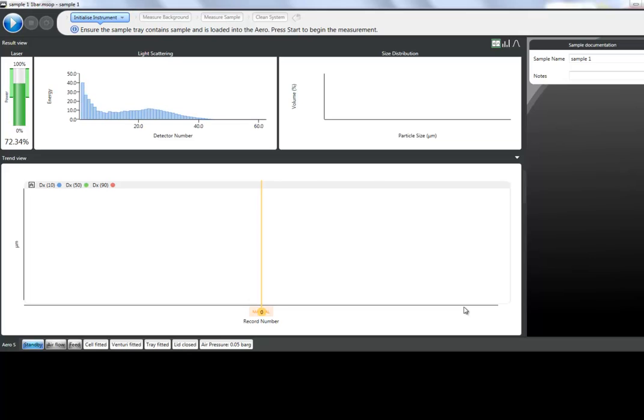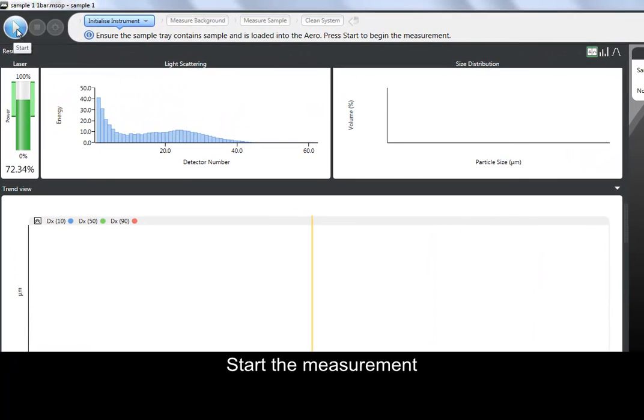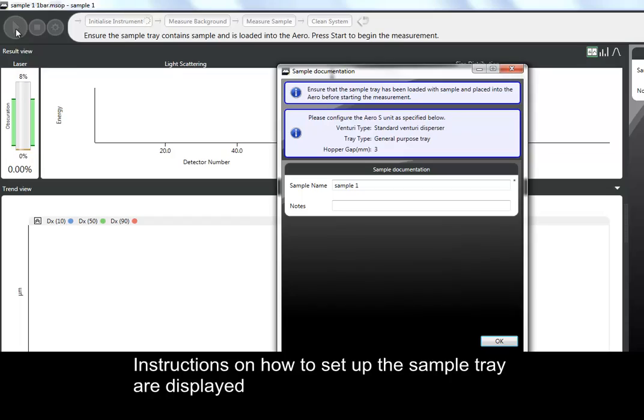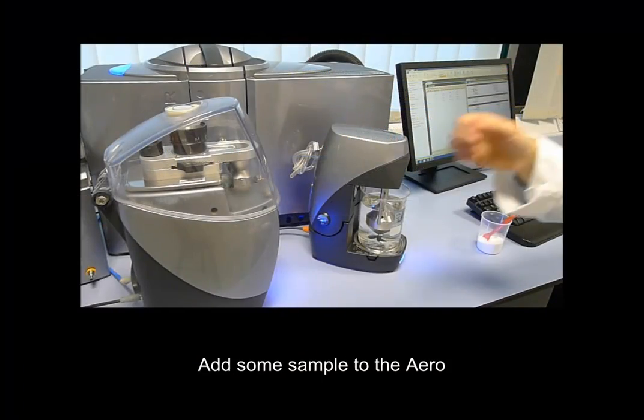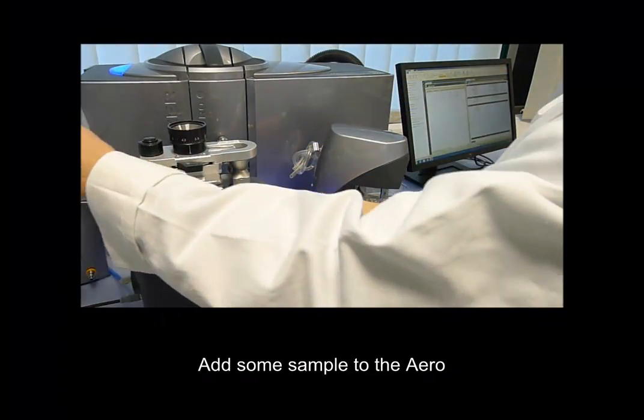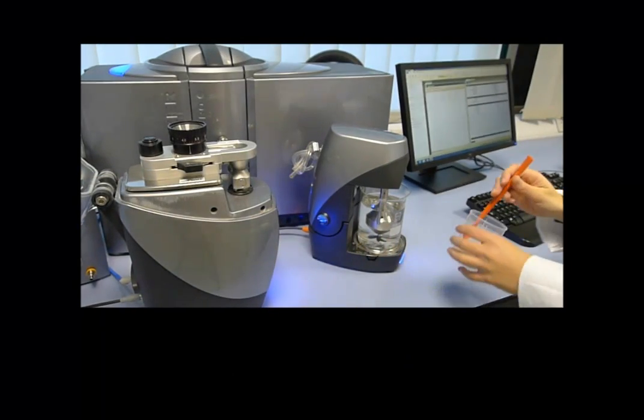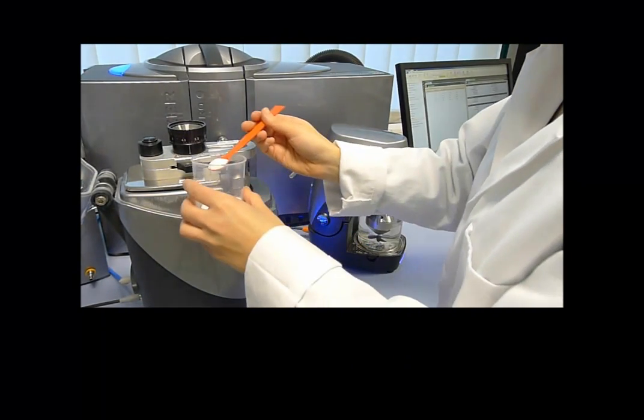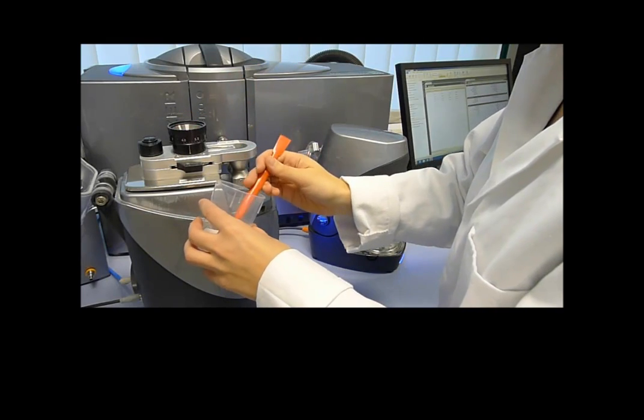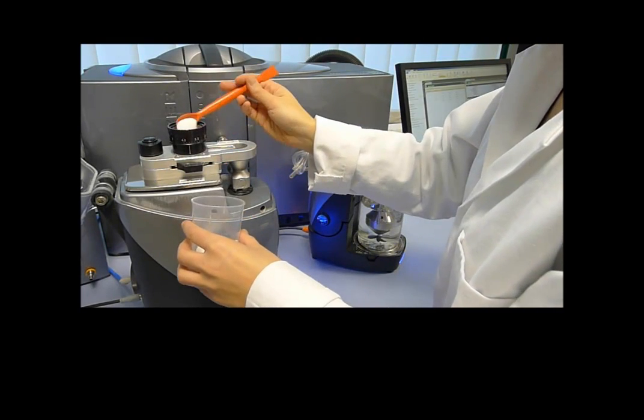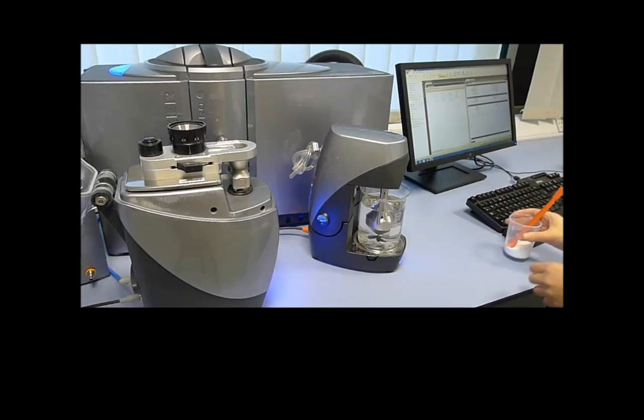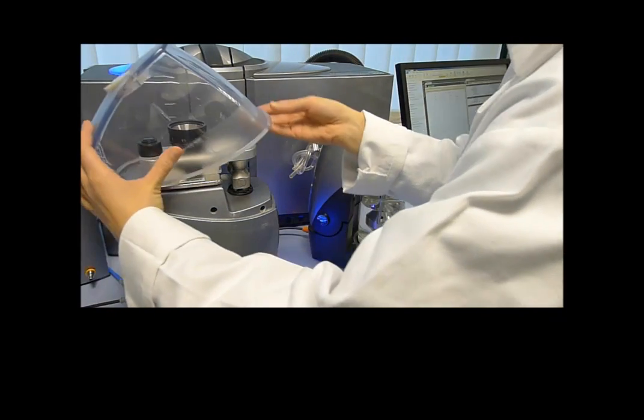So when we start the measurement, the sample details are displayed, along with the instructions on how to set up the Aero. So at this point, we need to put some sample in the Aero. And on the general purpose tray, the sample is added into the hopper, and we can adjust the height of the hopper in order to help control the flow of the material. And dry measurements are a good way to measure larger amounts of sample.